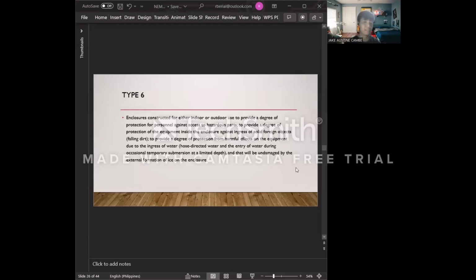So next type is type 6 NEMA enclosures. So it is constructed for either indoor or outdoor use to provide a degree of protection for personnel against access to hazardous parts. Next is to provide a degree of protection of the equipment inside the enclosure against ingress of solid foreign objects, for example, yung falling dirt, and to provide a degree of protection from harmful effects on the equipment due to the ingress of water. So, for example, yung hose-directed water and the entry of water during occasional temporary submersion at a limited depth. So, and that will remain undamaged by the external formation of ice on the enclosure.